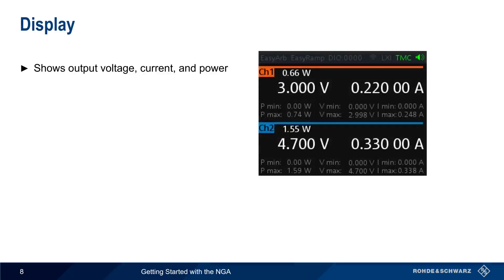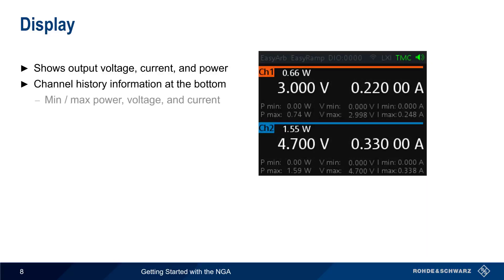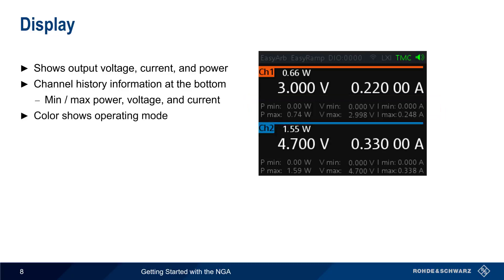The NGA displays the output voltage, output current, and output power updated in real time. For each channel, history information in the form of maximum and minimum values of power, voltage, and current are also shown. The color of the displayed values indicates the operating mode for each channel. White is used in editing mode, that is, when the output is disabled.